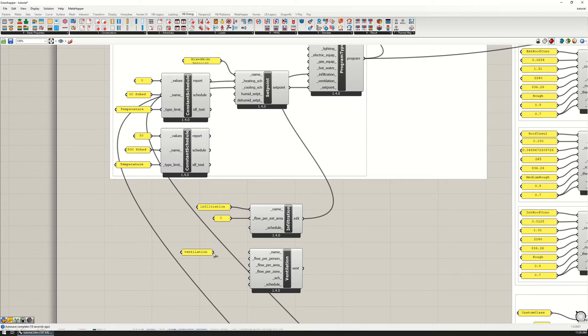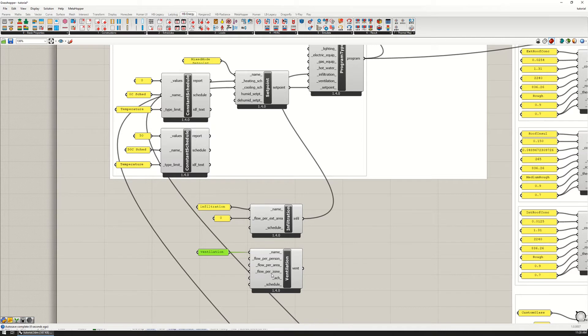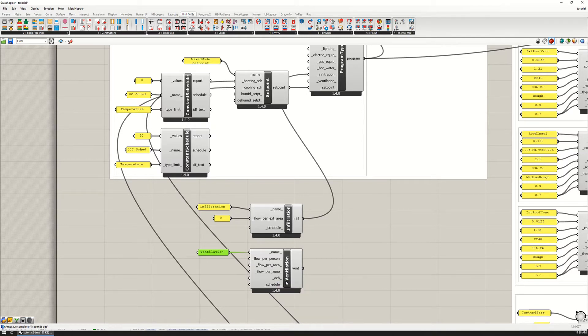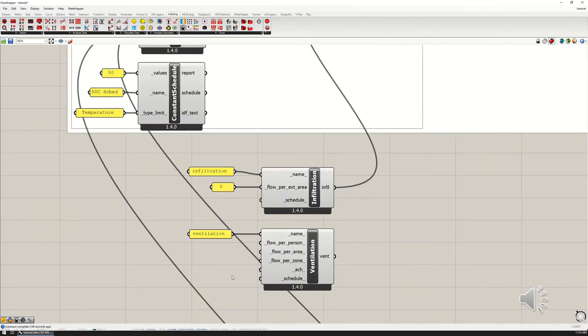It gives us a few different options. I can put in a name for the object and then I can have a flow per person, a flow per area, a flow per zone, or an ACH air changes per hour. This is the number of air changes in the zone, whereas all three of these are in cubic meters per second.